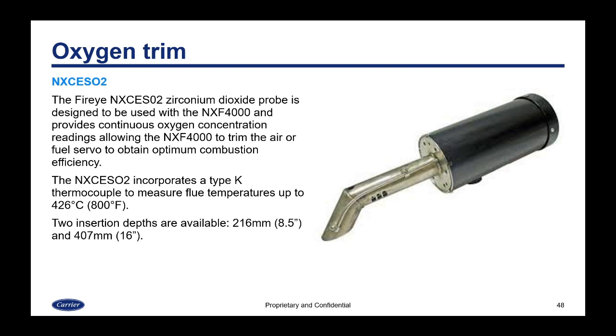The Fireye NXCES02 zirconium dioxide probe is designed for use with the NXF4000 and provides continuous oxygen concentration readings, allowing the NXF4000 to trim the air or fuel servo to obtain combustion efficiency. This is the oxygen trim system. The NXCES02 also incorporates a Type K thermocouple, which can measure the flue temperature up to 800 degrees Fahrenheit. This is available in 2 insertion depths, either 8.5 or 16 inch for the stack, as well as mounting accessories.